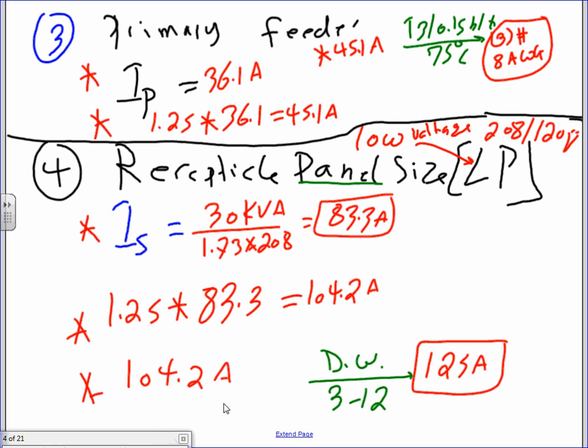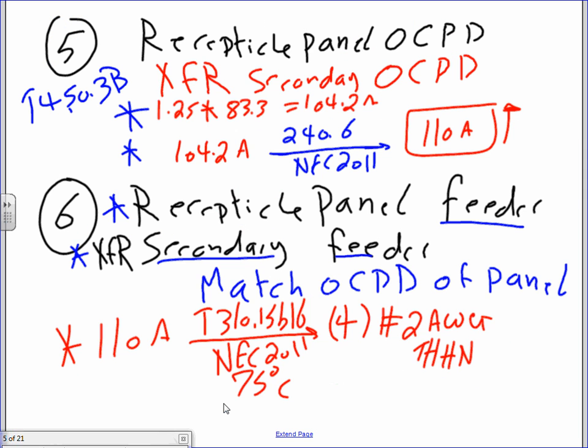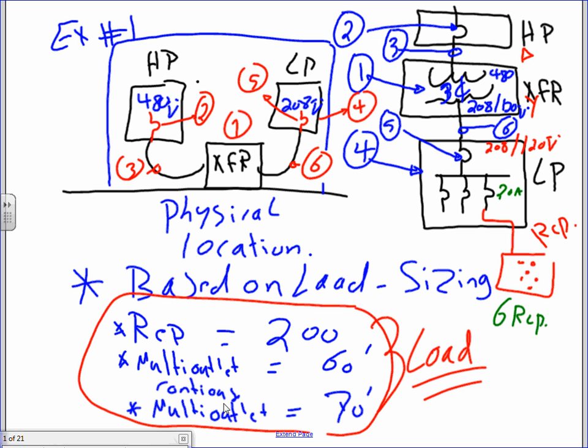Okay, I'm just trying to write the insulation. If you guys will write the insulation here, THHN, I always like to write the insulation for the conductors. There you go. So now we sized everything for this combo, ladies and gentlemen. Now let me take you back to where we started. We sized the transformer, the overcurrent protection device on the primary side, the feeder in the primary, the secondary feeder and the overcurrent protection device of the panel, as well as the panel itself. So you're good to go.